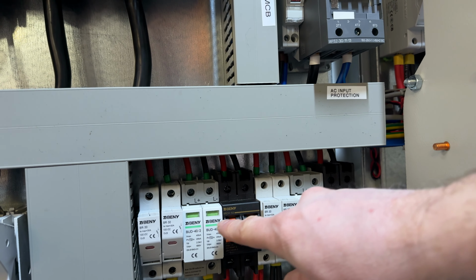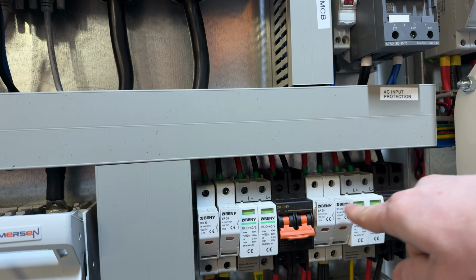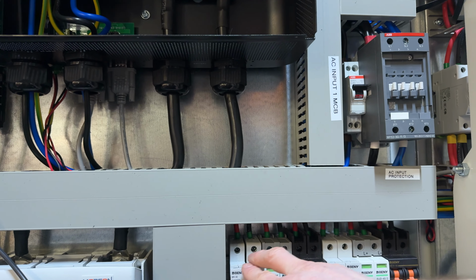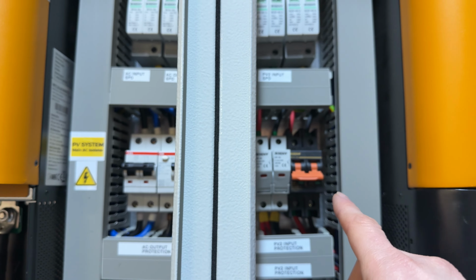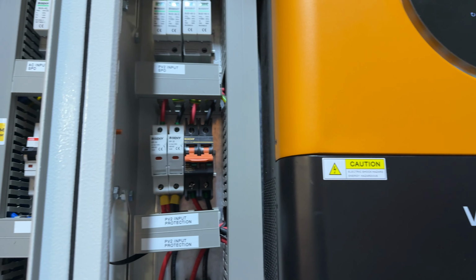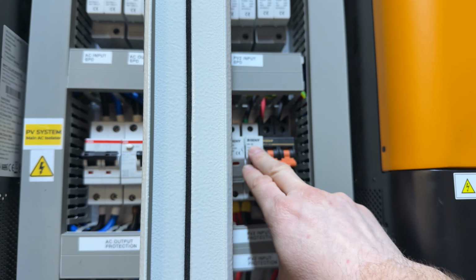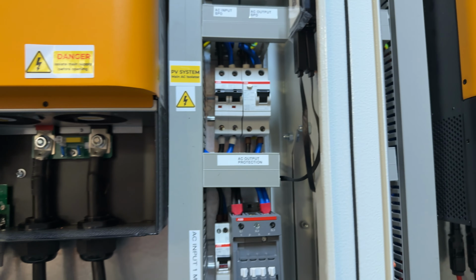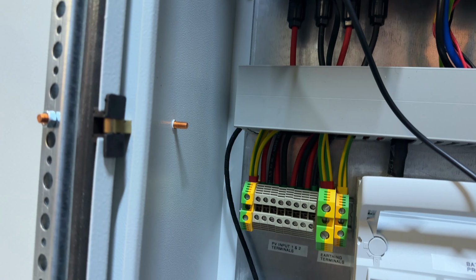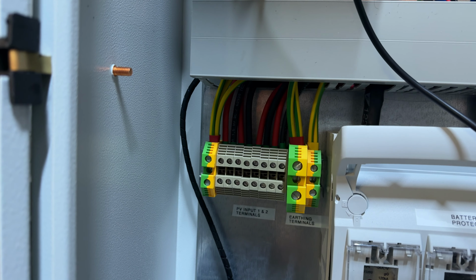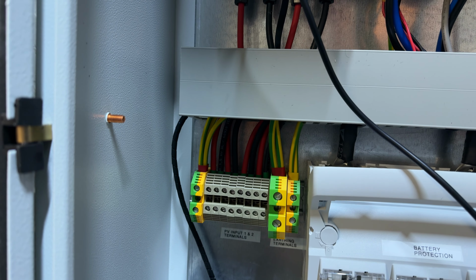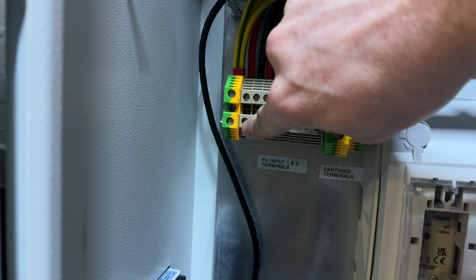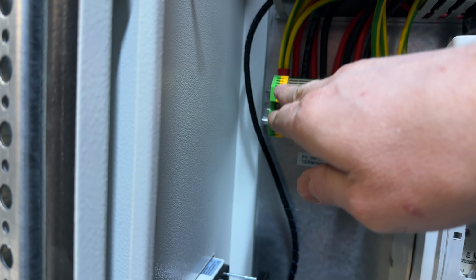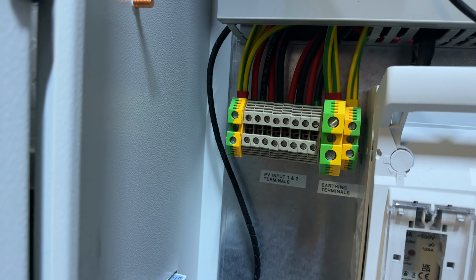On this side, we have the protection of the solar array. Your first inverter has two independent MPPTs, MPPT 1 and 2, and further on the right hand side we have the second inverter and the MPPT protection. That's for the solar PV 1 and PV 2. The maximum PV input is 450 volts, and you need a minimum of 6 to 7 panels in series to start one of these inverters. So make sure that you measure the voltage of the panels before you connect it to the inverter. And that's the input from PV1 and PV2. So you have 4 independent MPPTs here, as you can see.